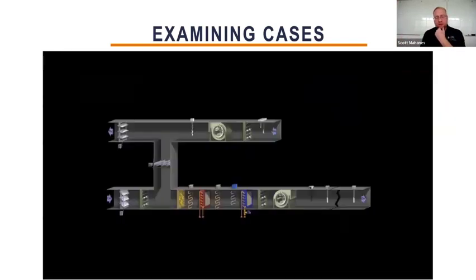Okay. And another kind of example of where this goes wrong is I might not be able to measure the outside airflow station correctly right here. And so I'll turn the unit into 100% econ mode. And if I'm smart, I'm going to actually neutralize this pressure right behind the mixed air damper, the return damper, so that I minimize any leakage from the return air system to this. And when I do this, I expect to have the same amount of airflow on the supply side as I do as the outside air, because it's all outside air sourced.